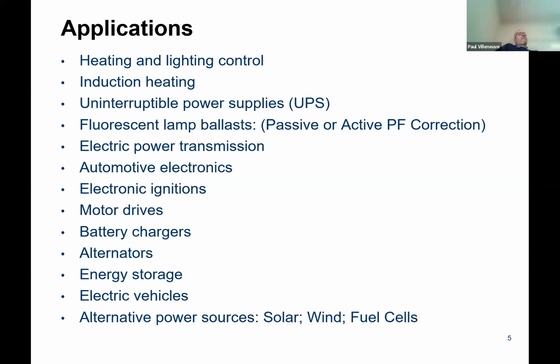You just completely discharge and recharge it? No, you try not to fully discharge or recharge, because that degrades the battery's life. Every once in a while you do, depending how critical it is. If I need a battery that can put out 400 amps for 8 hours and it's mission critical, I'd want to test it every year or every 5 years to make sure it can do it. But cycling a battery like that, drawing it all the way down, is really bad for it, so there are special batteries made to handle that. You try to keep your batteries fully charged as long as possible - they last longer. So if you drop it down to about half...